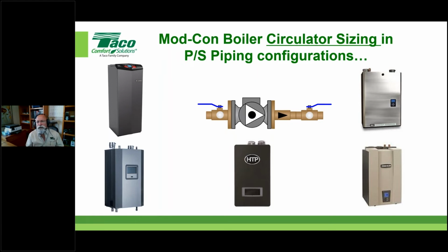But again, folks, I talk about this: if you do a good job of purging the big bubbles out, a really good job of the initial purging, the micro bubbles and the little tiny bubbles aren't what really hurt us a lot. When we get a call and they say this pump's not working or the boiler's going off on high limit, it's because it's full of air and no one did the initial purge. They think just filling up the system does all the work for you, like in our case, the 4900. No, it doesn't. You have to do the initial purge correctly.